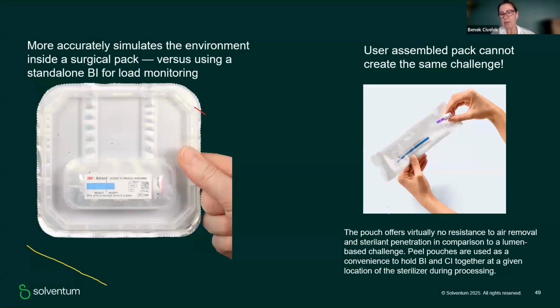We have been using maybe the right practice because we cannot put biological indicators alone. We need a Tyvek pouch to place the biological indicator together with a chemical indicator. But this is not a process challenge device. It is not tested accordingly. So it cannot give this lumen-based challenge. And therefore, when you put something like the right picture yourself, this is something only to hold the BI and CI together. But on the left side, you are working with a more challenging and tested, confirmed technology.